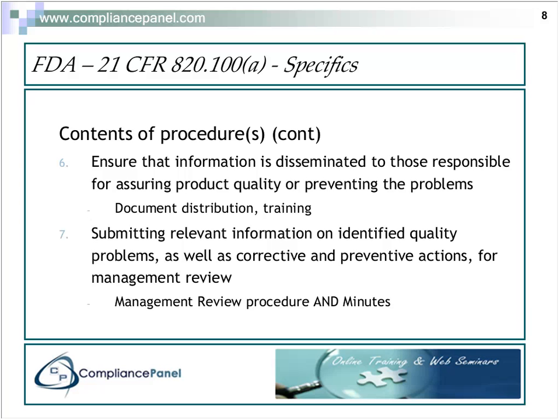So now CAPA has not just touched itself, the CAPA system, it has gone to document control, it has gone to training, and now it's going to management review. Your management review procedure must reference your CAPA procedure. It must state that all CAPAs will be reviewed by management for efficacy and adequacy, and also it must appear on your minutes.